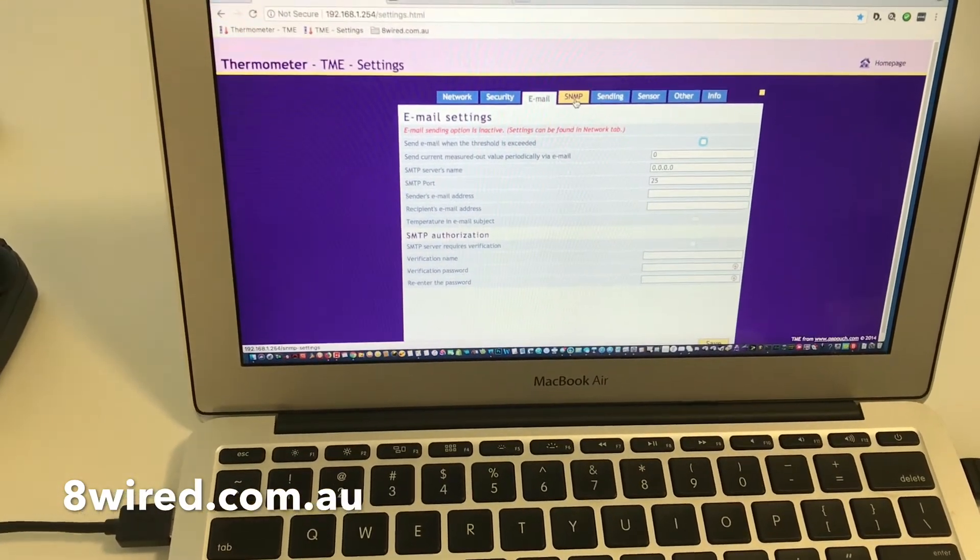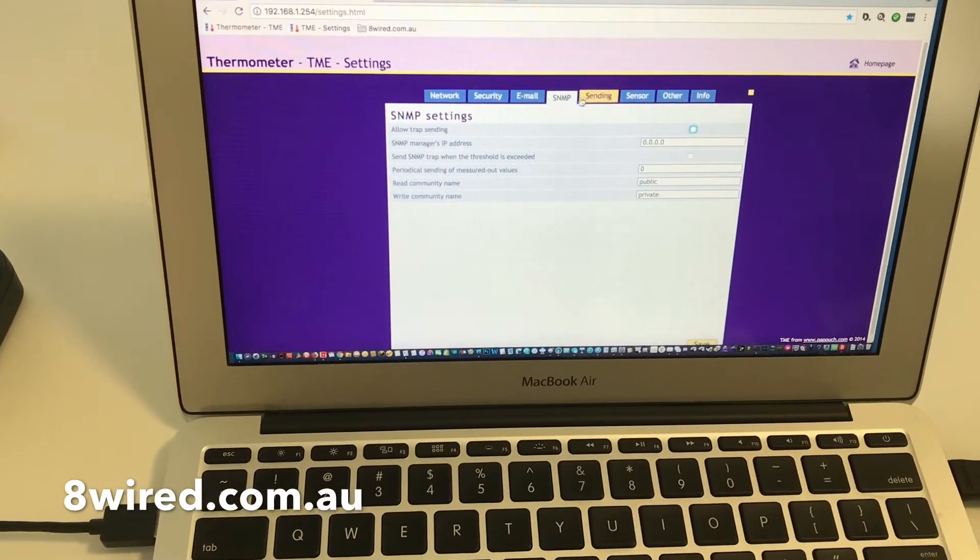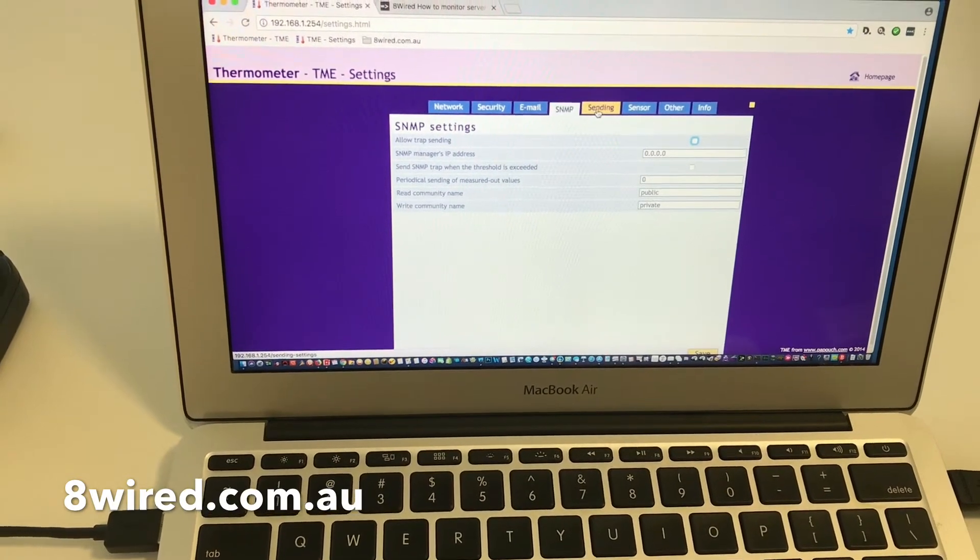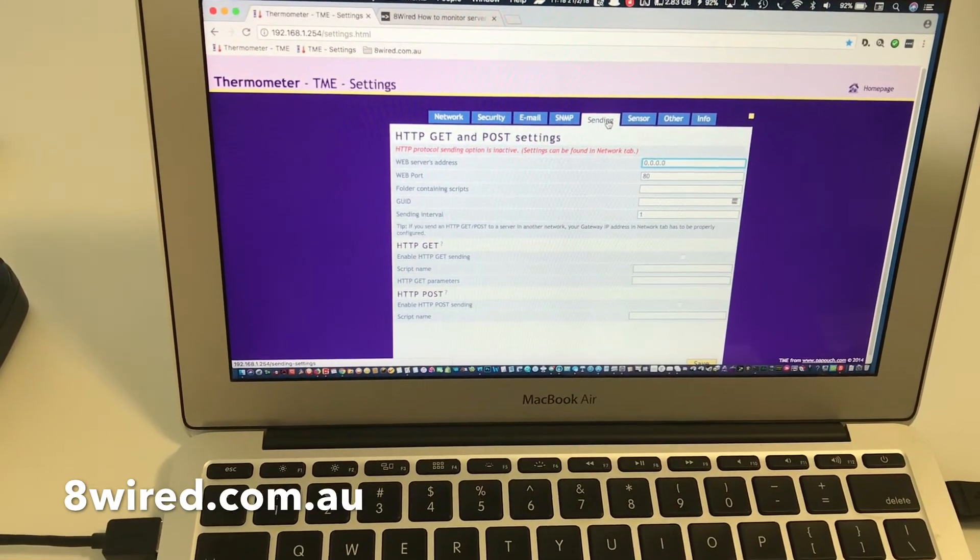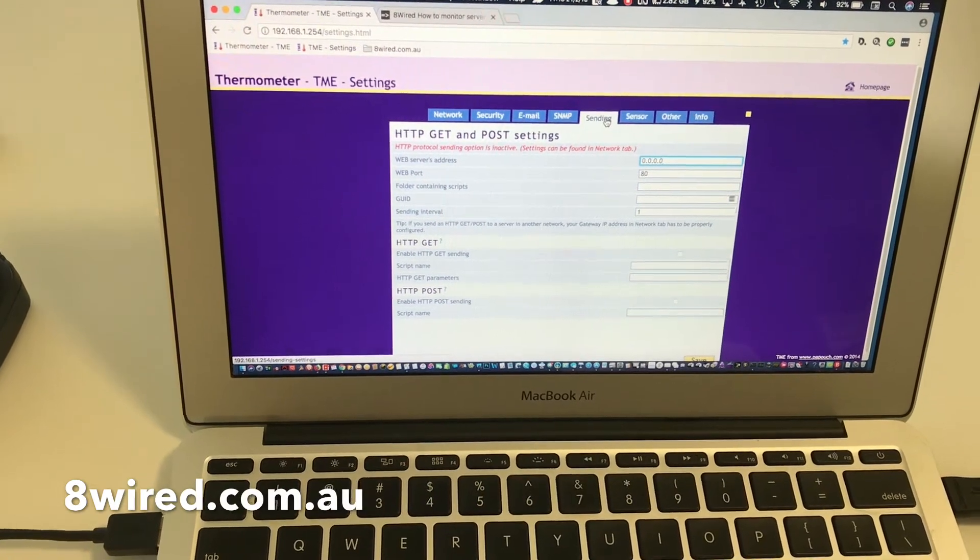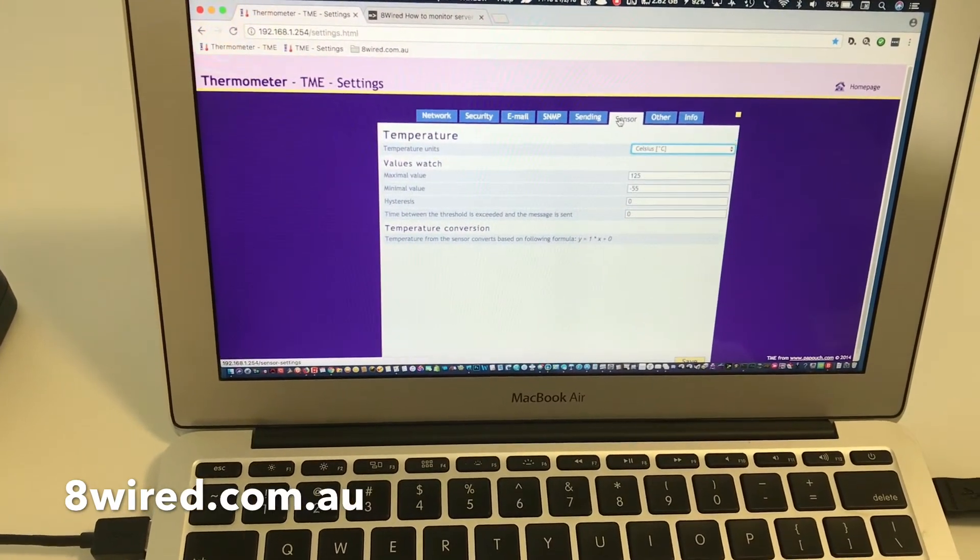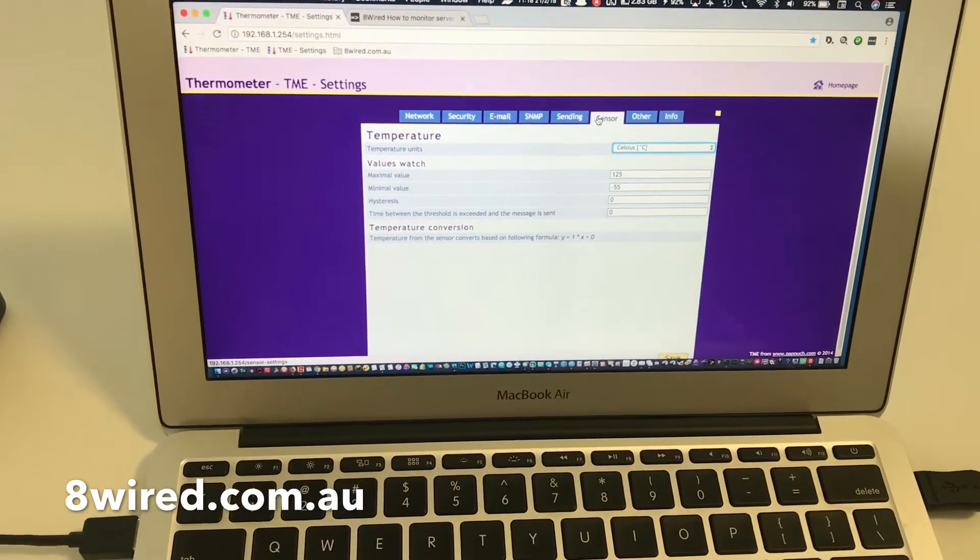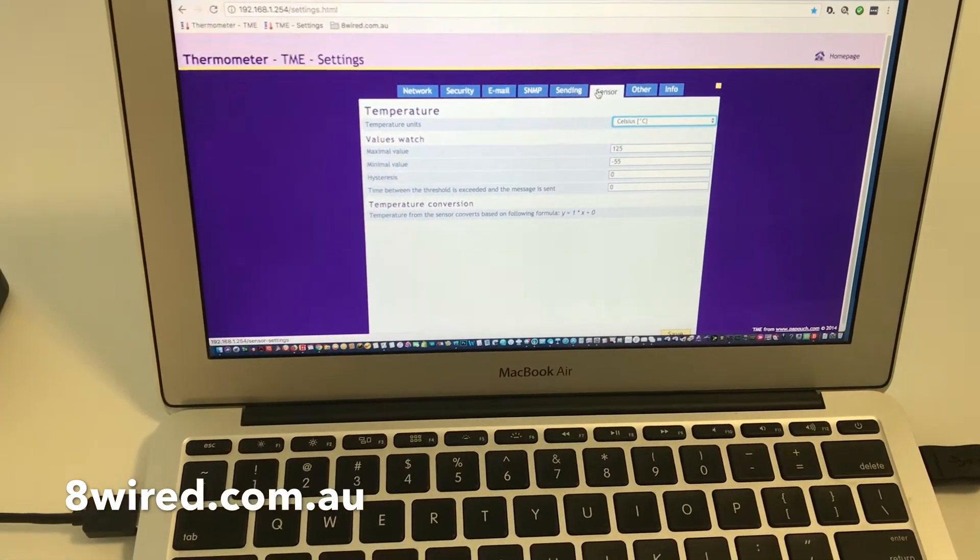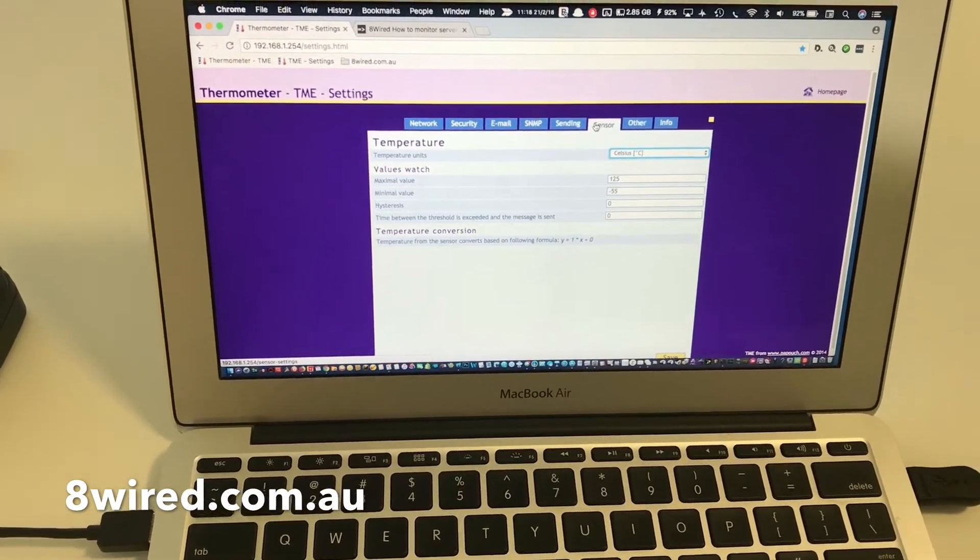You can set up SNMP if you want to get some management happening there. You can do email or POST and GET for HTTP and also configure the sensor minimum and maximum values. So you can set a range from anything that suits your environment.